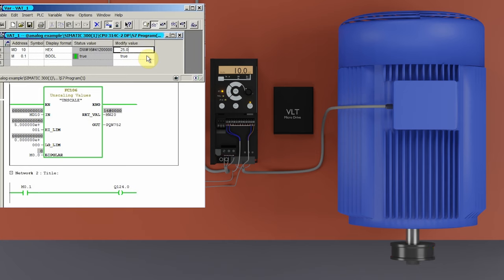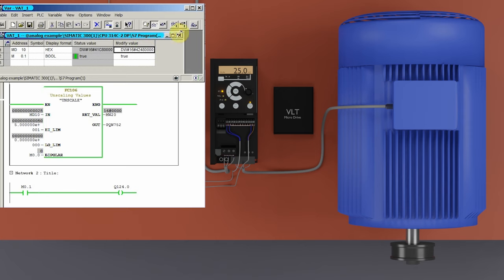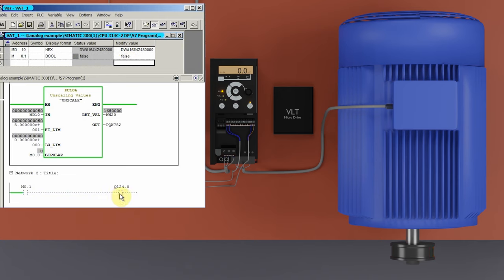Now if we set the MD10 register value to 25 in the variable table, the VFD output frequency changes from 10 to 25 Hz and the motor runs at 25 Hz frequency. Now if we set the MD10 register value to 50 in the variable table, the VFD output frequency changes from 25 to 50 Hz and the motor runs at 50 Hz frequency. Now if we turn off run command bit M0.1, it will turn off the run command relay and VFD output frequency goes to 0 and stops the motor.